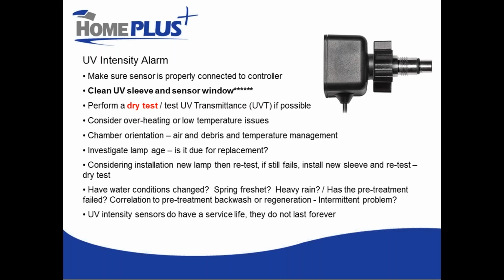Hardness minerals, iron, manganese, natural organics, sometimes even biofilm, like dead bacteria, especially if you have heavy bacterial loads in your raw water, can potentially accumulate on that sleeve, and over time they will reduce the amount of UV light that can pass through the sleeve. I actually have an example in one of my other presentations where I show a UV sleeve that is completely orange. It had about a 32nd of an inch of iron deposits built up on it. That UV sleeve, no UV light was getting through it.